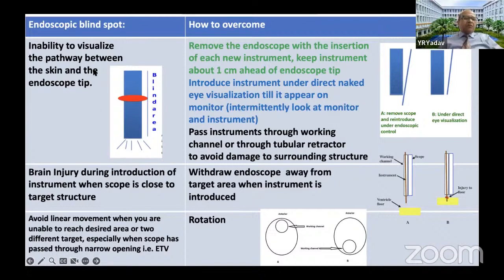The other limitation is that there may be brain injury during introduction of the instrument when the scope is close to the target area. This is the example. Supposing you are doing an ETV, this is the floor of the third ventricle, and if your endoscopic tip is very close to the floor and you pass an instrument, any of the ventriculostomy forceps or catheter or bipolar forceps, then suddenly the instrument will appear and you may cause damage to the target area, the floor, or whatever tissue is there.